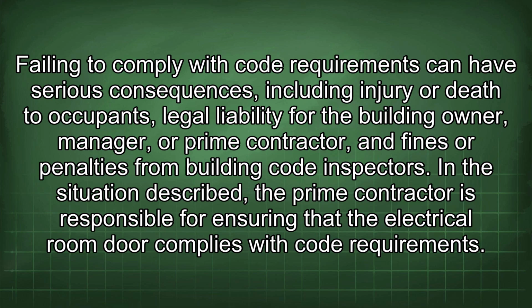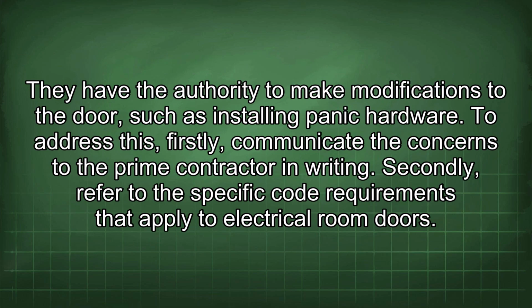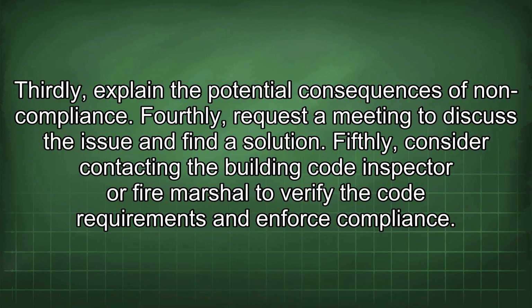In the situation described, the prime contractor is responsible for ensuring that the electrical room door complies with code requirements. They have the authority to make modifications to the door, such as installing panic hardware. To address this, firstly, communicate the concerns to the prime contractor in writing. Secondly, refer to the specific code requirements that apply to electrical room doors. Thirdly, explain the potential consequences of non-compliance. Fourthly, request a meeting to discuss the issue and find a solution. Fifthly, consider contacting the building code inspector or fire marshal to verify the code requirements and enforce compliance.